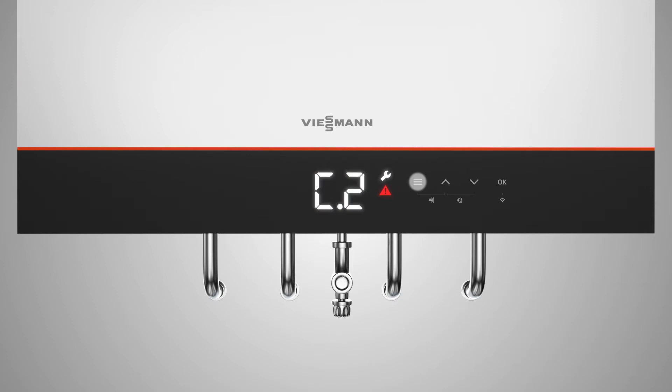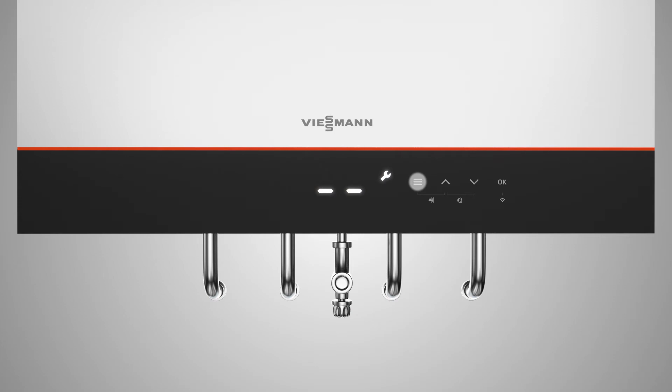Starting the venting program. To follow the next steps, please always press OK. The display shows the pressure in bar. If the display shows two dashed lines, please check the pressure sensor located below the boiler. To end the venting process, press the menu button for approximately 4 seconds until the next step appears.